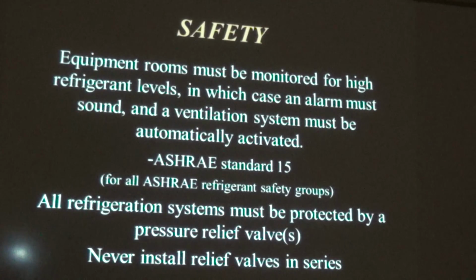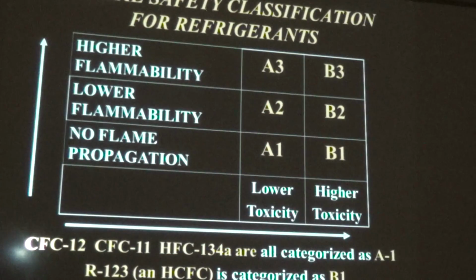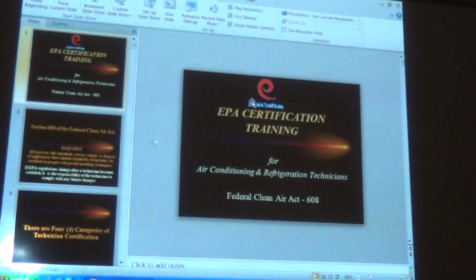All refrigeration systems must be protected by a pressure relief valve. Here's the question, here's the answer. Never install relief valves in series. They're going to ask, can you install them in parallel or something to that effect. And here's the ASHRAE chart right here. And here's where they point out R123 is a B1. And that's the end of the story.